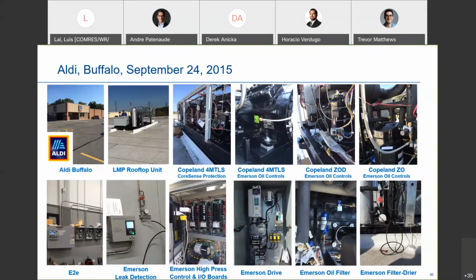We've got our liquid line filter dryer, the STAS, our AOFD, our oil line filter dryer. You've got the Control Techniques drive, high pressure controls down here in the middle. That controls the high pressure, the bypass valve, and here's your valve driver. The brains are in white. The valve driver is on the right. You've got leak detection as well as E2. There's a lot of Emerson stuff on there. It's been operating for the last 5 years at an Aldi store in Buffalo.